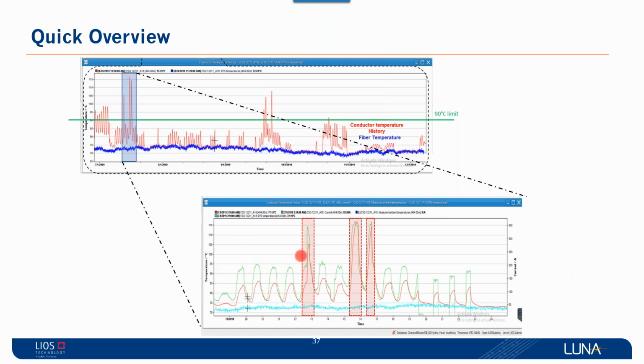So peak hours coming down and the conductor temperature goes up. It is clear that you can go around 100 and 250 amp automatically. Every time the load goes above 250 amp, this triggers a conductor temperature of about 115 degrees Celsius. This is way beyond the 90 degrees Celsius limit.